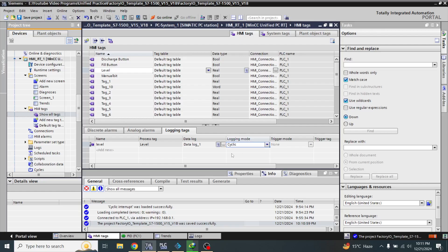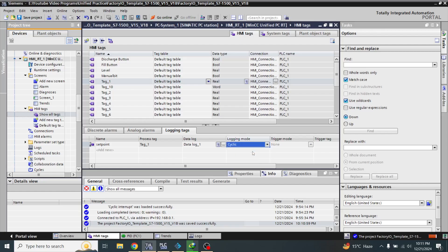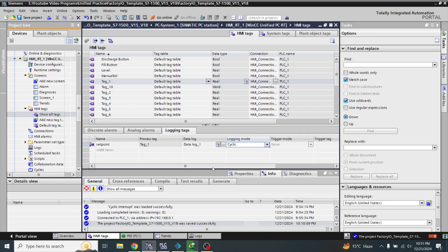Now I am going to change it to cyclic because I don't need the logging tag on change, because that only saves when the value changes. Now it is going to save every second. So my logging tags are now created.